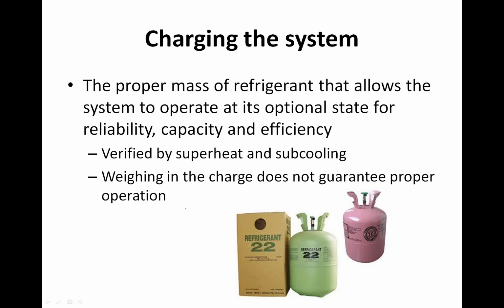I don't care what manufacturer you deal with, because I talk to people that put in mini splits and put in large commercial systems and all kinds of stuff. Somewhere down the line, the manufacturer has charged that system up by superheat and subcooling. So if you're putting in a packaged rooftop and it tells you that it requires 10.2 pounds of refrigerant, somebody has charged that system up using a subcooling or superheat method to get that charge exactly what it should be, and then they weighed that refrigerant into the system and know how much exactly has to go back into that package unit, right? But all systems are charged by superheat and subcooling.